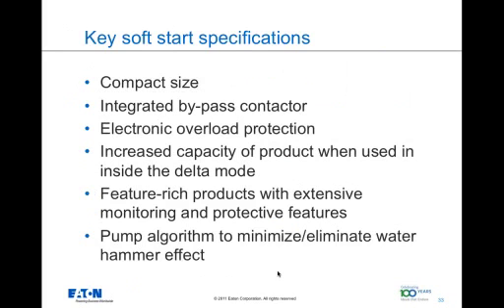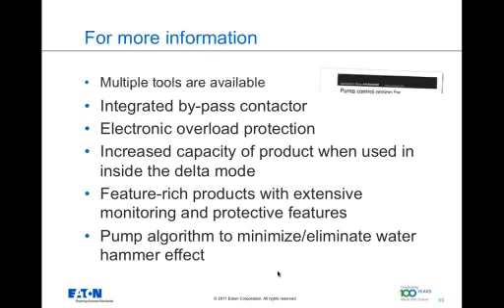This slide talks about some of the key specifications that are requested by the general customers out there. Generally, the customer is looking for a compact-sized soft starter with an integrated bypass, electronic overload protection, feature-rich products with extensive monitoring and protection capability, pump algorithm to minimize and eliminate water hammer, and for customers having 6-lead or 12-lead motors, they would like to have a soft starter which can work inside the Delta configuration. That kind of a requirement typically comes from the elevator industry or from the HVAC marketplace.